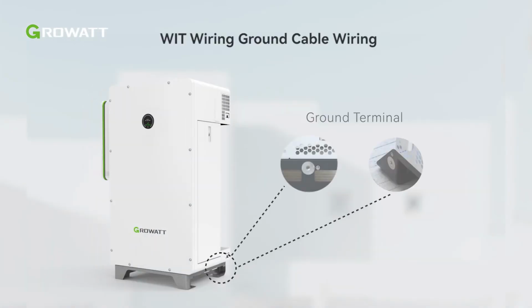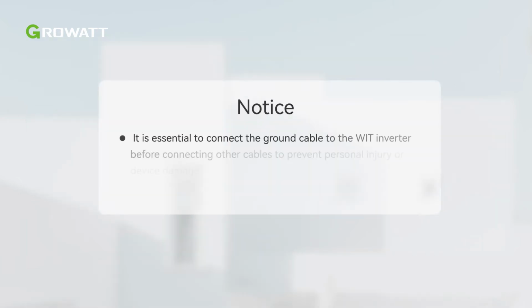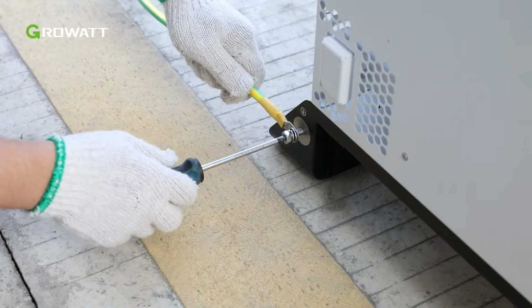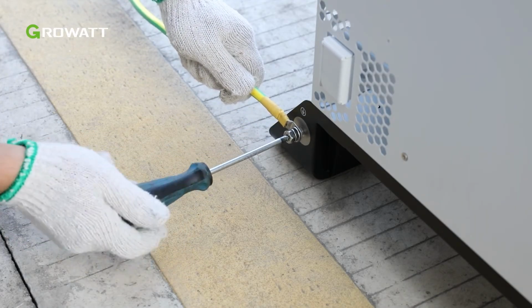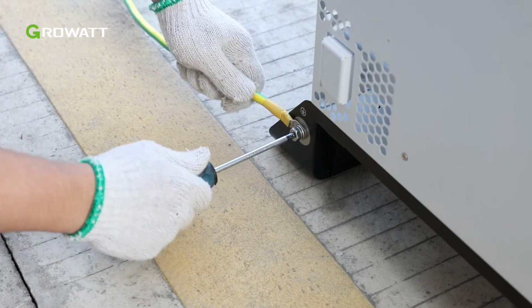Before starting wiring the inverter, make sure it is safely and firmly grounded. Notice: it is essential to connect the ground cable to the WIT inverter before connecting other cables to prevent personal injury or device damage. For a single WIT inverter, connect a ground cable to the ground point on the chassis shell.